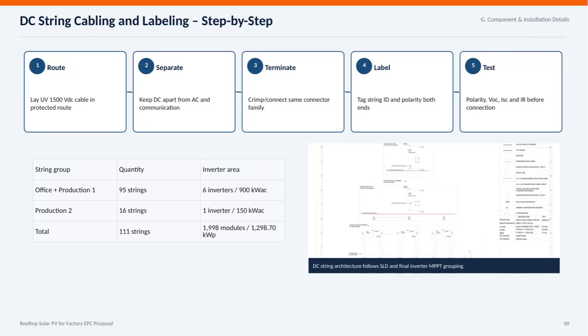Let's walk through the DC string cabling and labeling process step by step for our rooftop solar PV system. First, we lay the UV 1500 VDC cable in a protected route to ensure durability and safety. Next, it's important to keep DC cables separated from AC and communication lines to avoid interference. Then, when terminating the cables, we use connectors from the same family to maintain consistency and reliability.